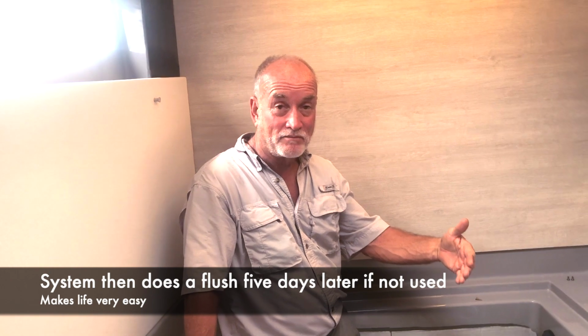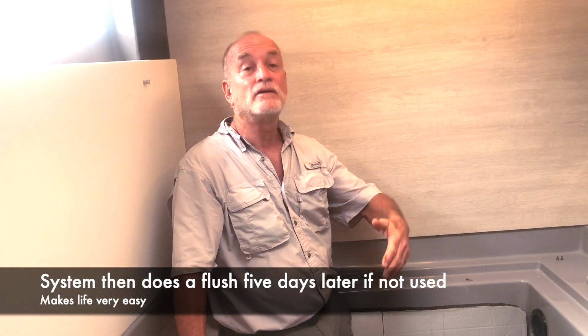she's going to go into a 120-hour, basically 5-day countdown. If you don't make water in that 5-day period, the countdown will go to 0, and then she'll flush herself again, go right back into another 5-day countdown, and it'll just do that indefinitely. If you're going to leave it for 2-3 months at a time unused, then we'll talk about storing it with that propylene glycol.